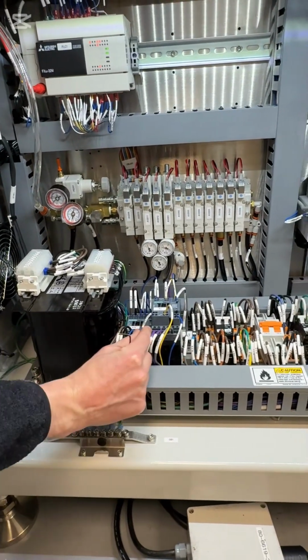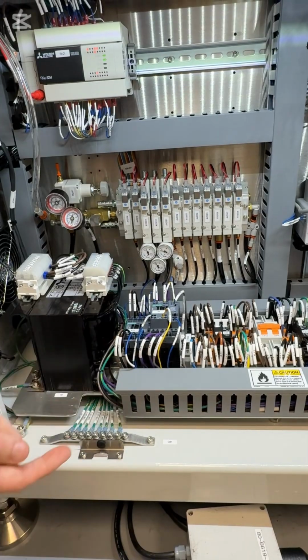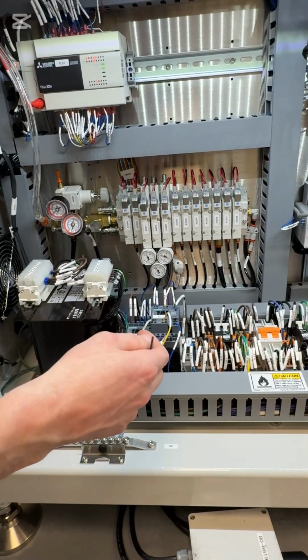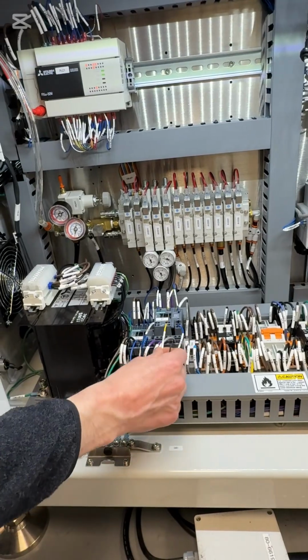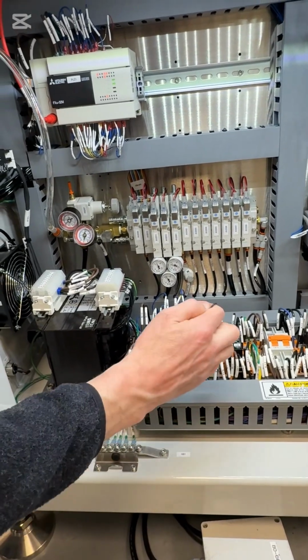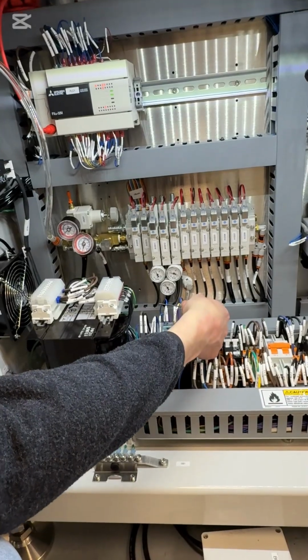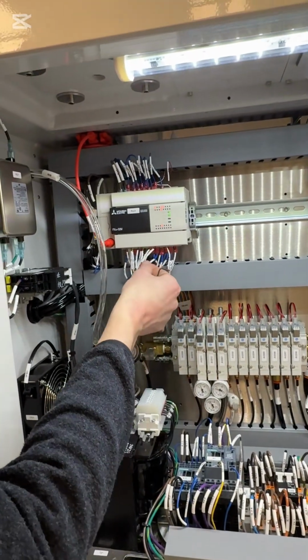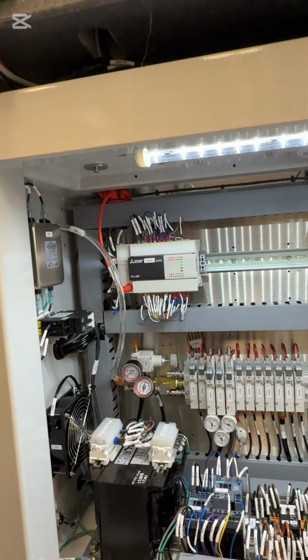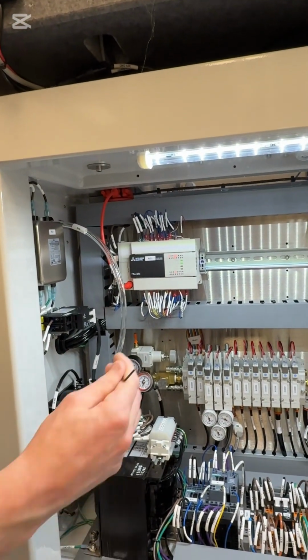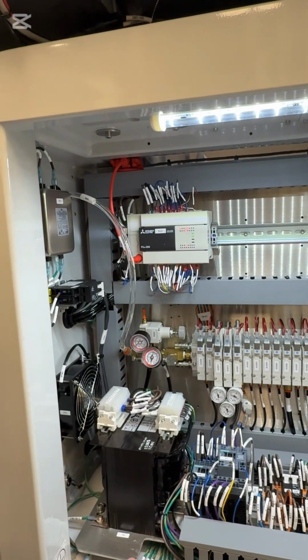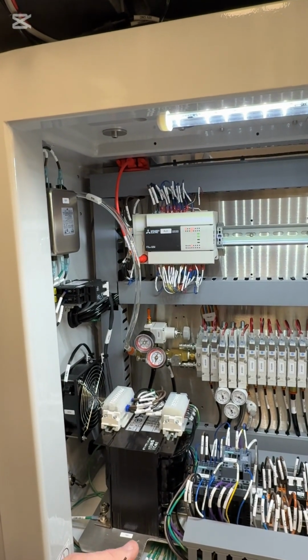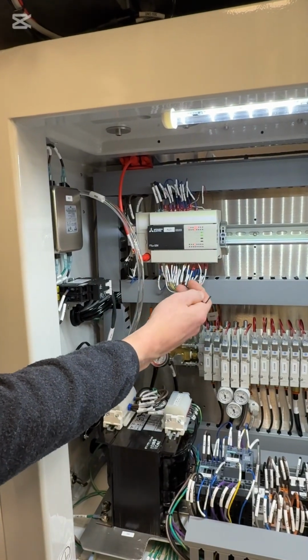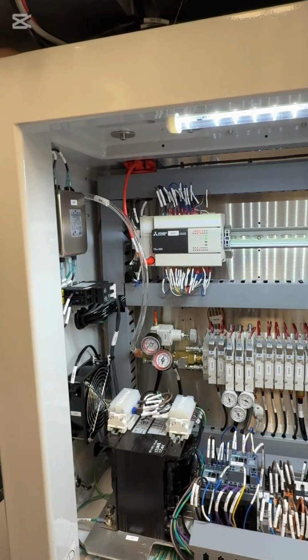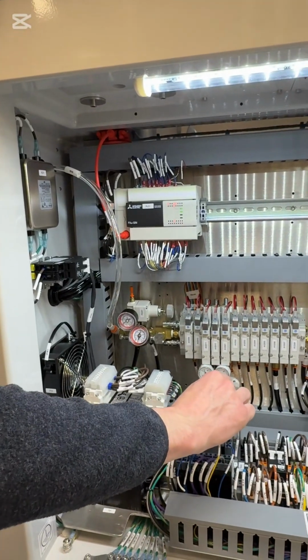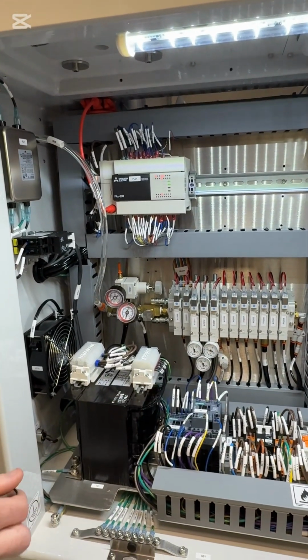You can see this signal here. This says amps enable. This is coming from the interface modules. The blue button is the amplifier mode, which is the voltage to the amplifier. And this signal here, Y11, goes directly to the PLC. So it's communicating with the PLC. It gives it the condition that the amplifiers are in. And if you have a problem with this signal, Y11, if the conditions aren't met, then you're not going to be able to activate the K1 contactor.